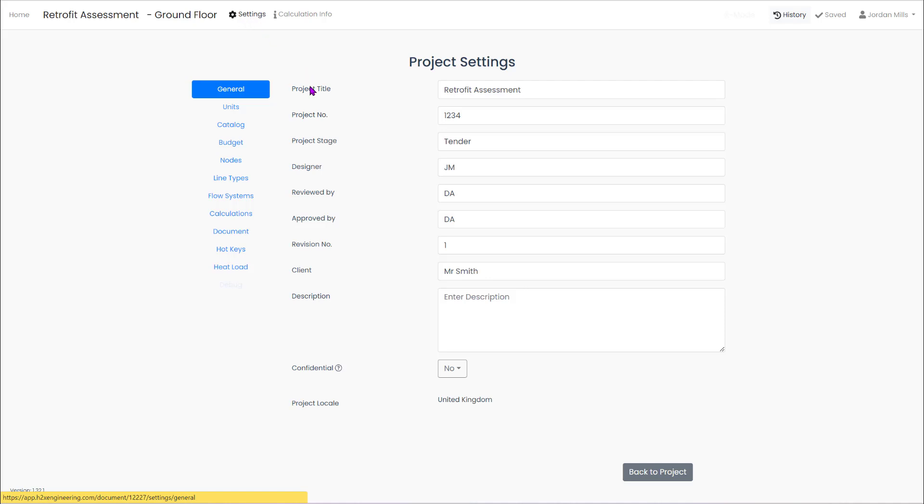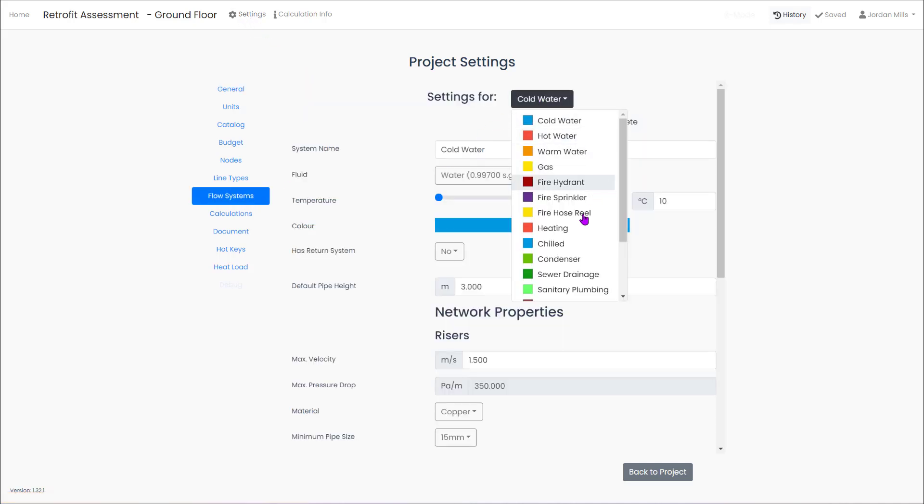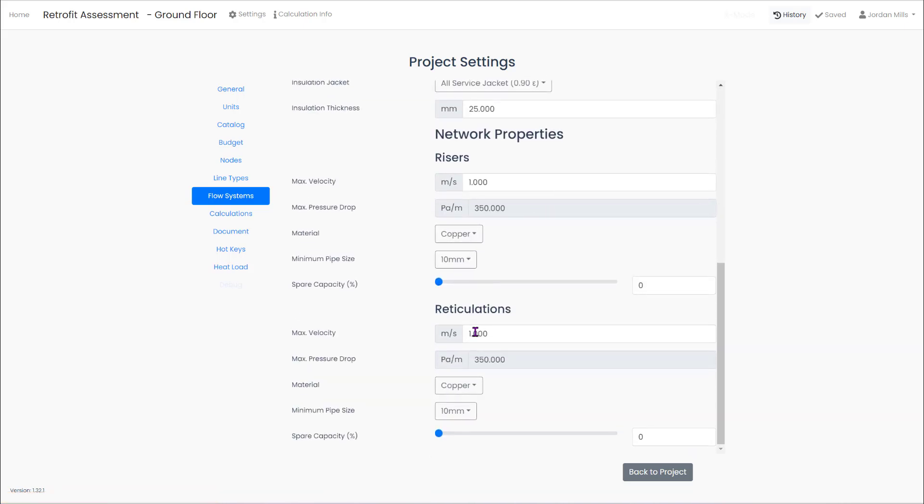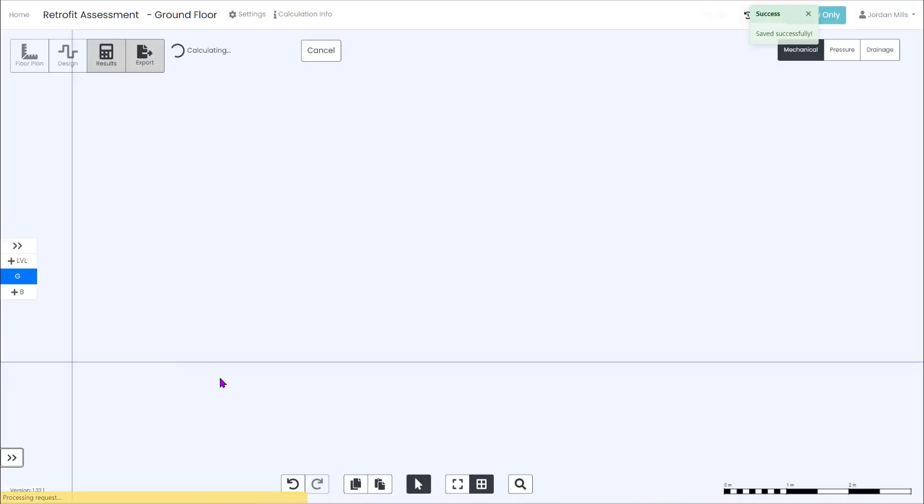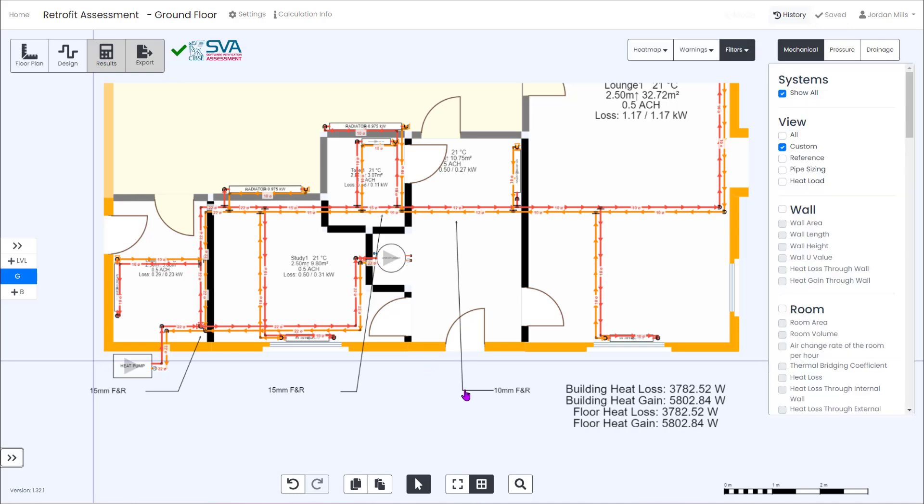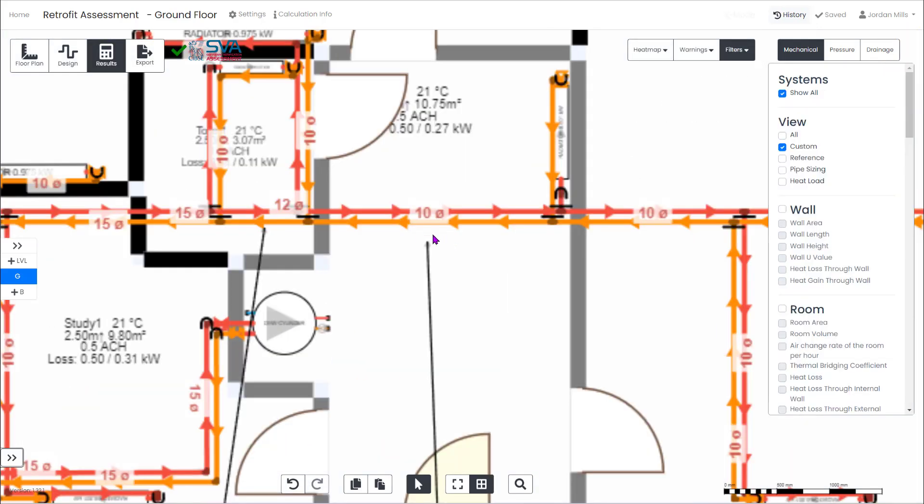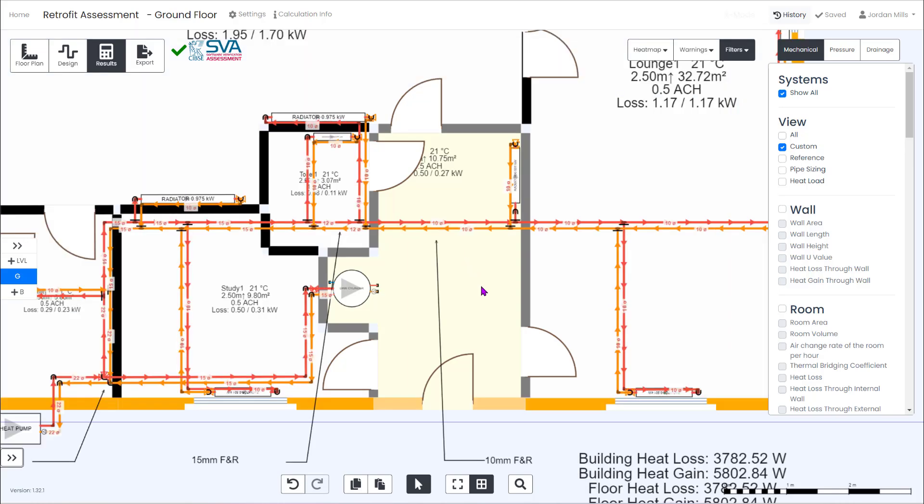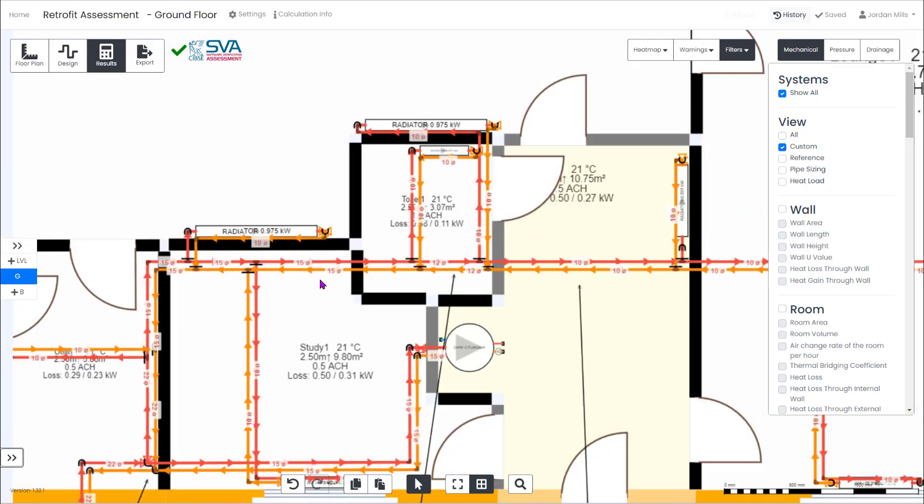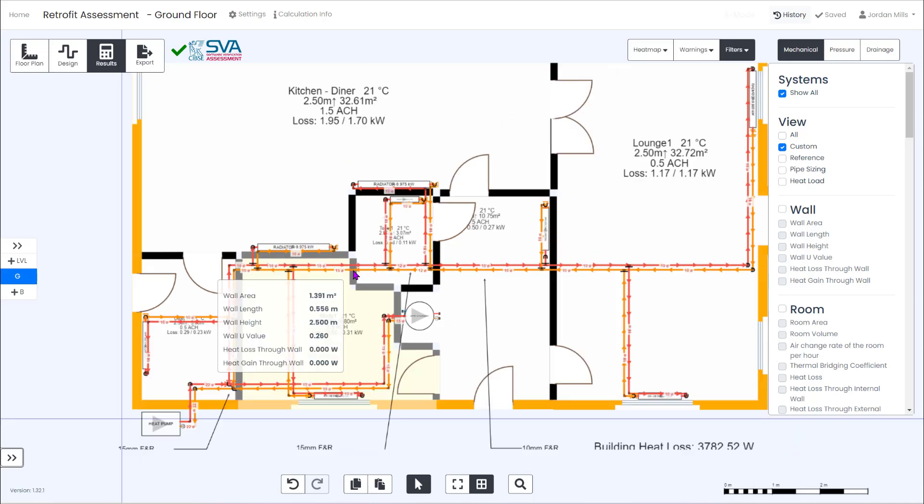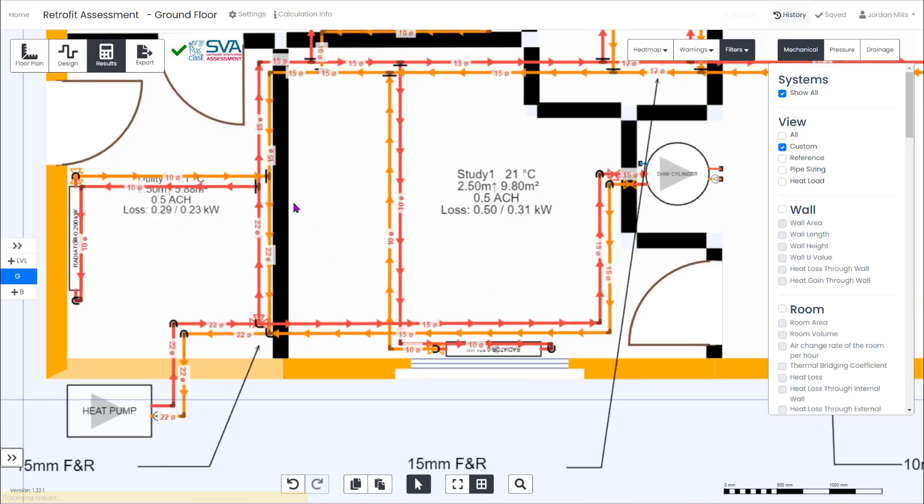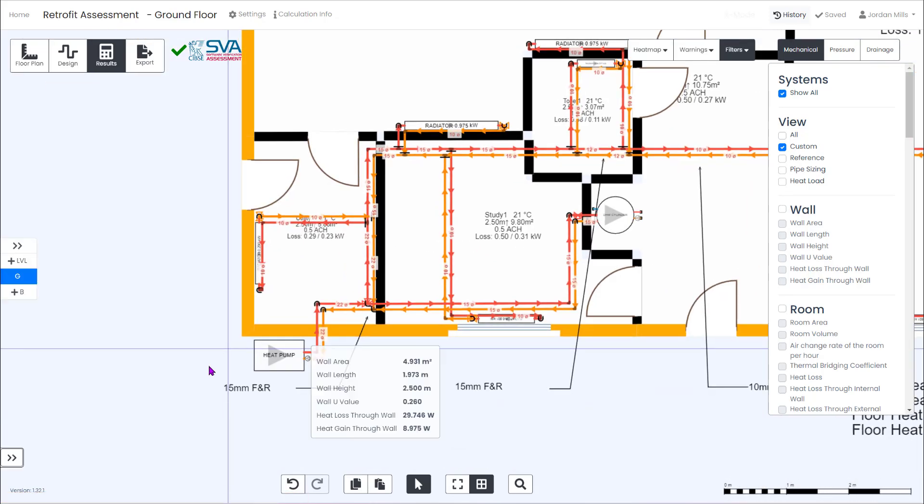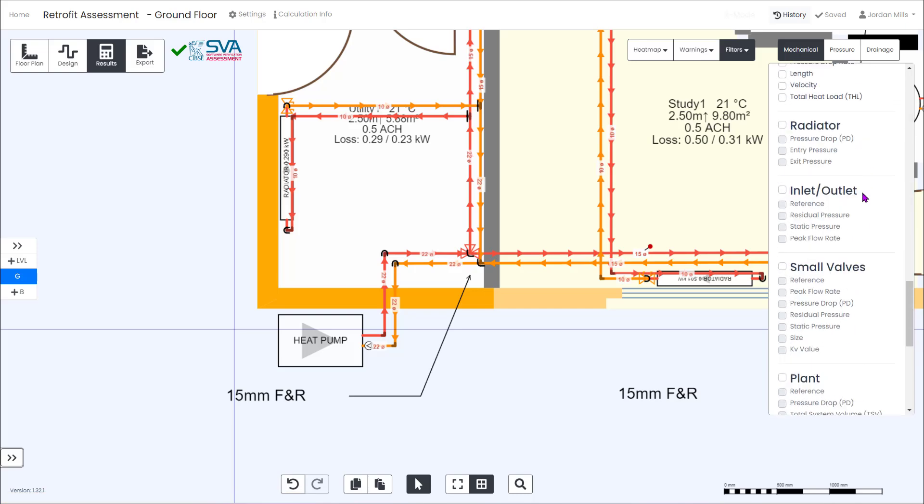So to avoid this we could have a play around with our maximum velocity. It defaults to the recommended one meter per second but if you wanted to push the envelope a bit you could try going up to a maximum of 1.5 meters per second. Checking the results again we can see that we now only need a 22 mil to the first radiator. We don't need to replace any existing pipe work through the study. The hallway's dropped to 10 mil which is great. This really minimizes unnecessary expense, work and disruption for the customer.